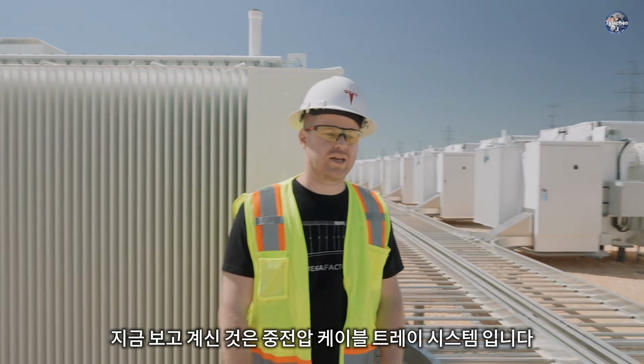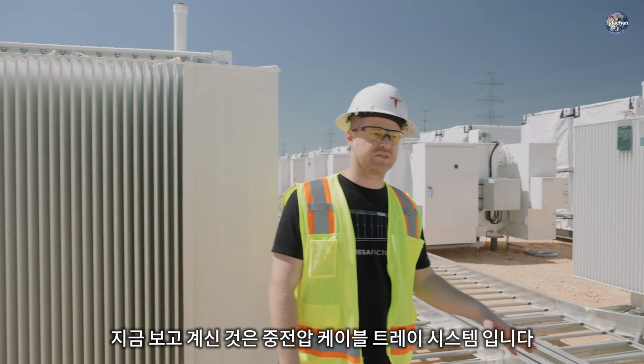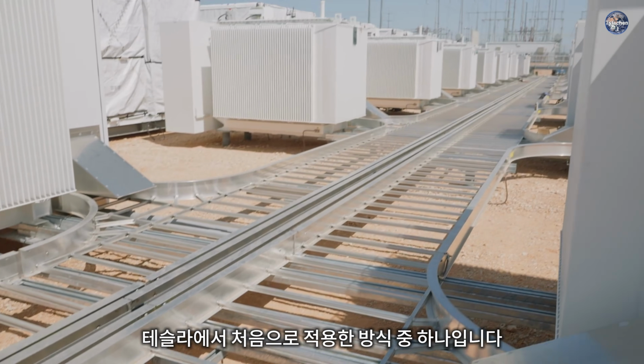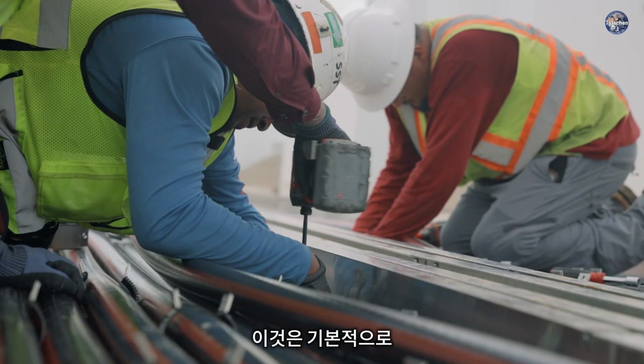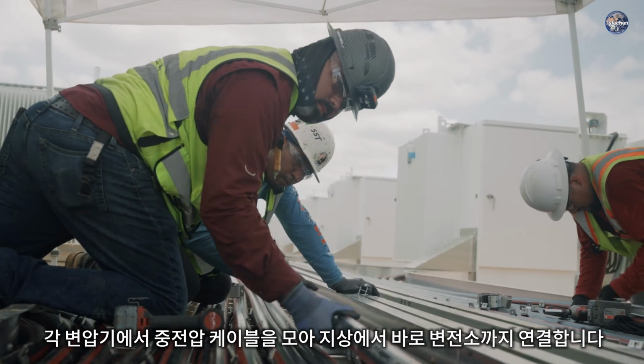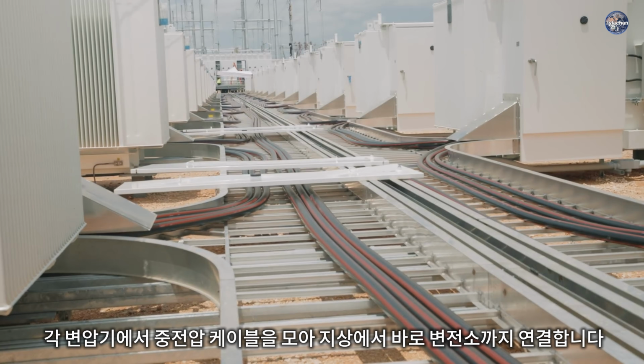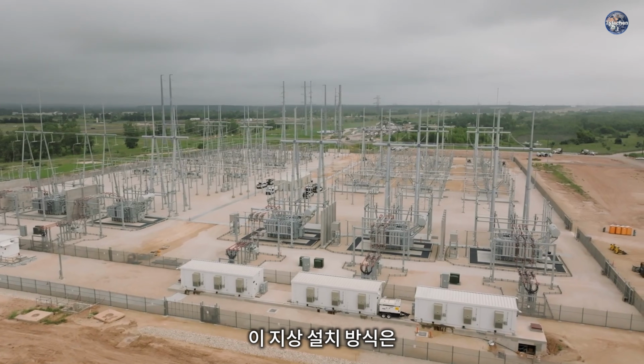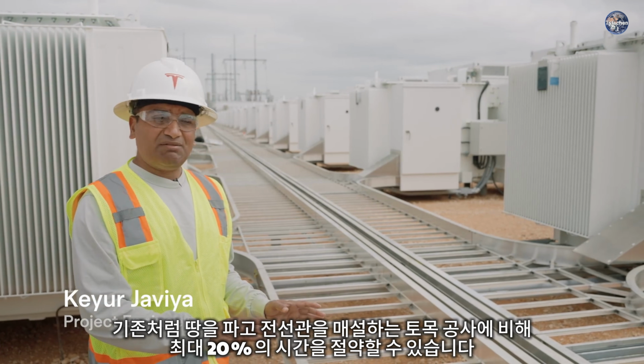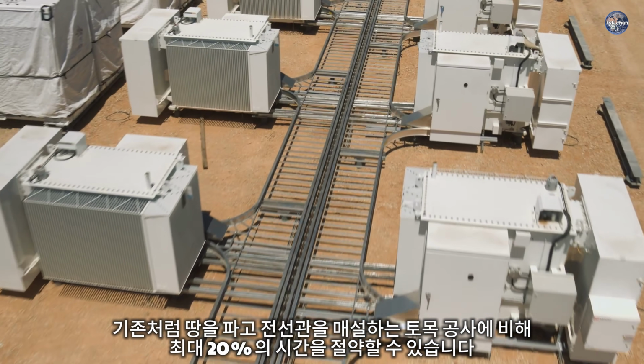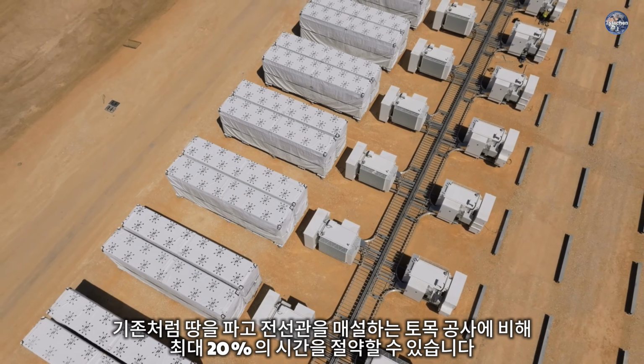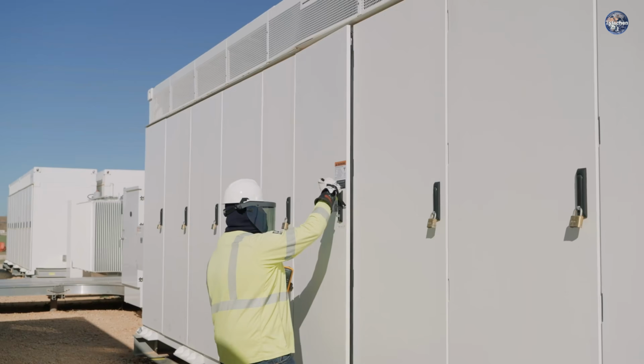What we are looking at here is the medium voltage cable tray system, which is one of the first that we have done for Tesla. This essentially collects medium voltage cables from each transformer and routes them above grade directly to your substation. This above ground application can save up to 20% of the time compared to the regular civil work needed to dig the site and install the conduits.